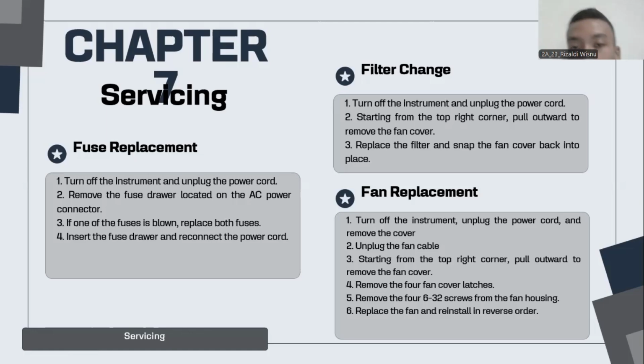Okay, next is filter change. Number one, turn off the instrument and unplug the power cord. Next, starting from the top right corner, pull outward to remove the fan cover. Number three, replace the filter and snap the fan cover back into place.